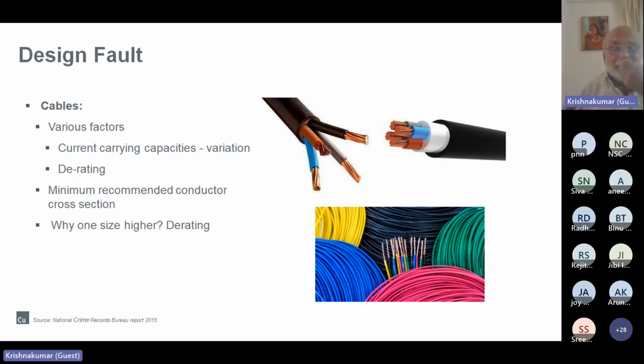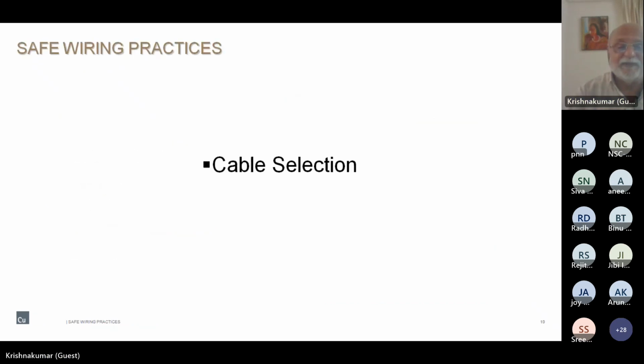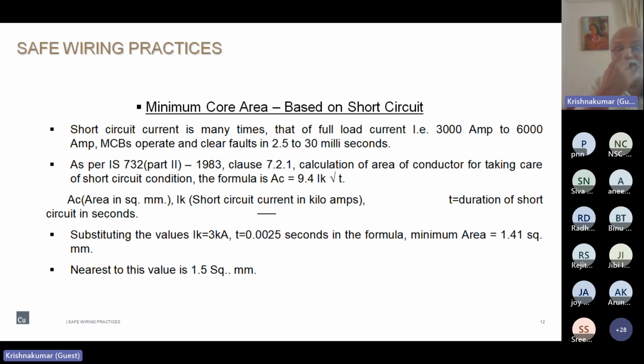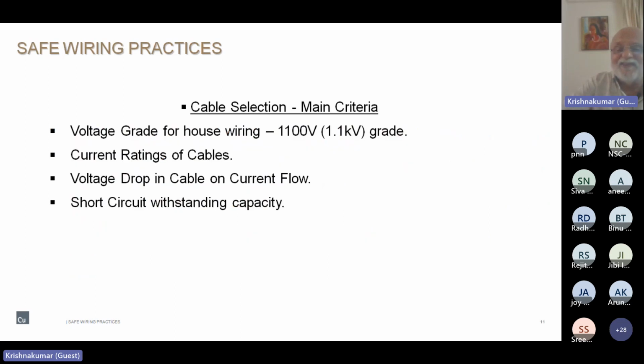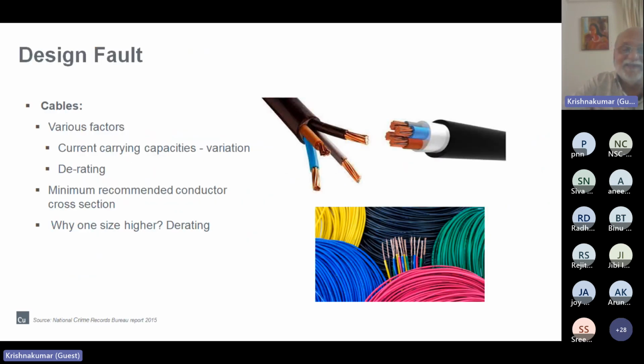One, the earlier I told about the short circuit withstand capacity. The technical experts have assessed that, in order that the copper conductors do not go beyond 100 degrees temperature within the short span of the MCB tripping time, the minimum cross section has to be 1.5 square mm. But unfortunately this is not observed by our people.